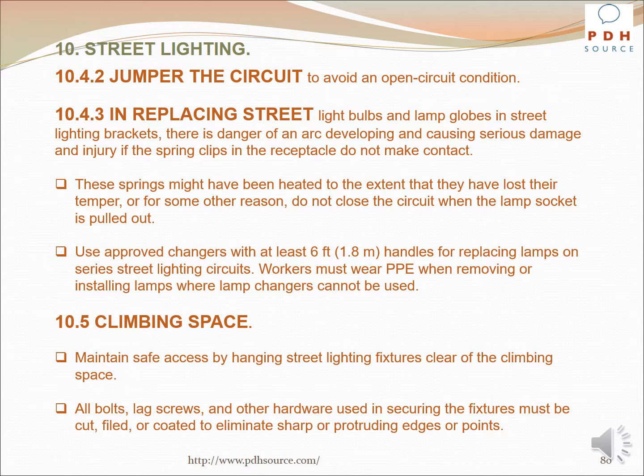In replacing street light bulbs and lamp globes in street lighting brackets, there is danger of an arc developing and causing serious damage and injury if the spring clips in the receptacle do not make contact. These springs might have been heated to the extent that they have lost their temper, or for some other reason do not close the circuit when the lamp socket is pulled out. Use approved changers with at least 6-foot handles for replacing lamps on series street lighting circuits. Workers must wear personal protective equipment when removing or installing lamps where lamp changers cannot be used.